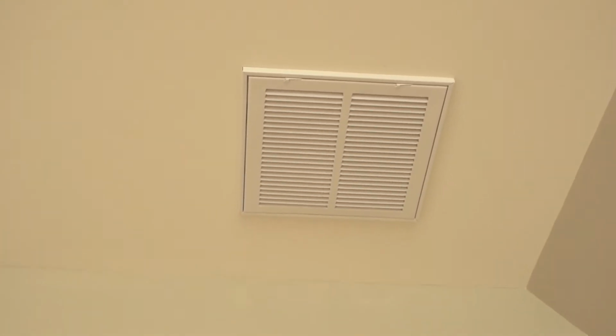And then one of the big things is we're sitting in this bonus room. And the same thing is true for bedrooms, any rooms that get air fed to them. In this room, if you notice down here in this corner, we have a jumper duct. Right. And as we're trying to feed air into this room, normally if we don't have a path for it to get back to the unit, it's like trying to blow air into a full bottle. We can't get it in here. So what happens is the air inside the main body of the house continues to turn over, but this room doesn't get the cooling it needs and it doesn't get the dehumidification.